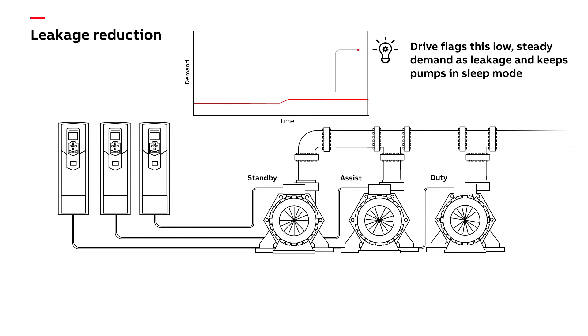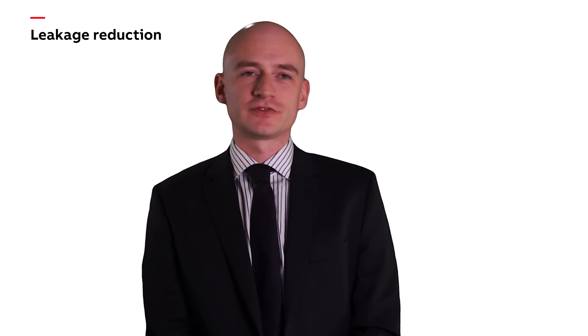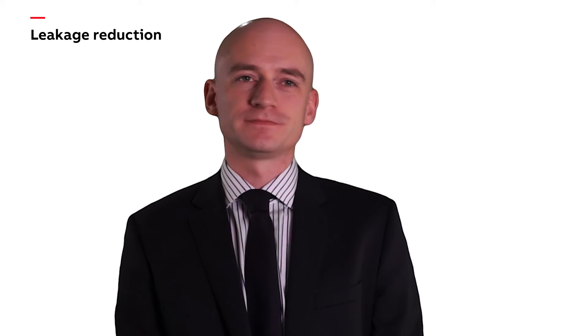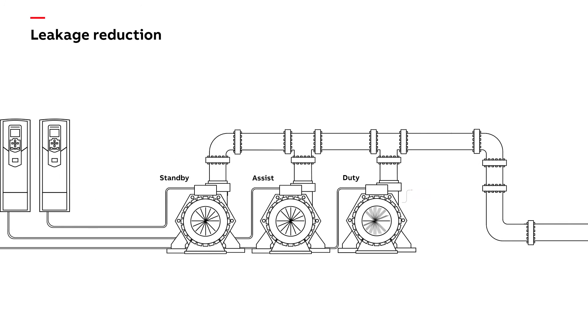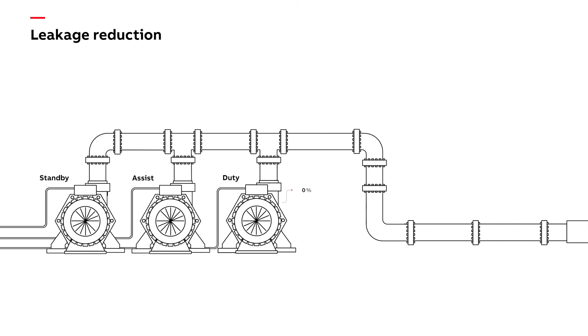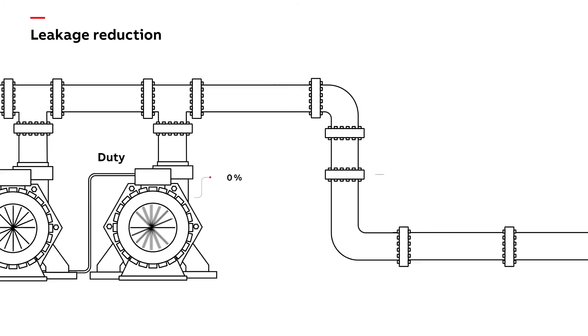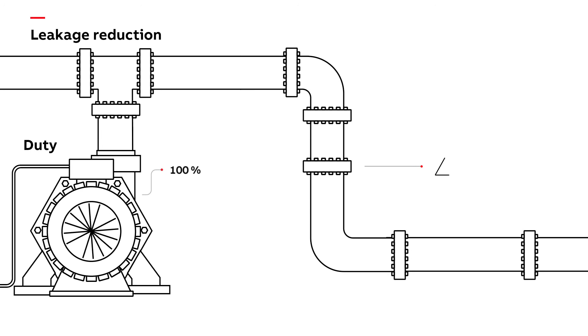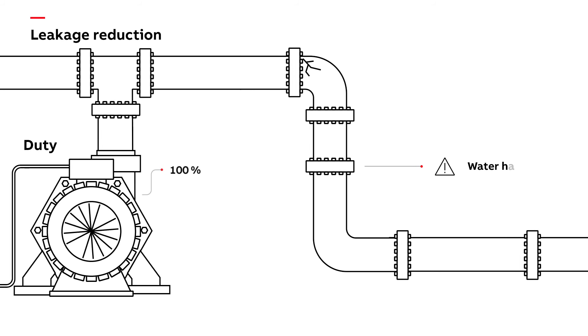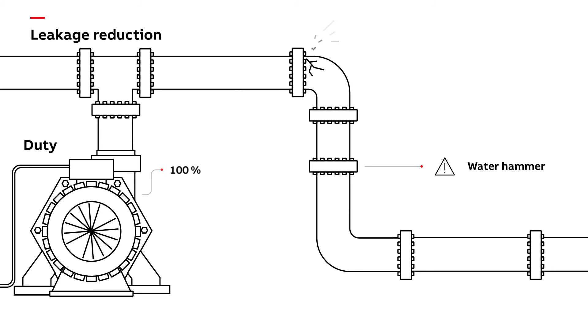Drives can also prevent leaks from occurring in the first place. Switching pumps on and off causes rapid changes in flow. These flow changes are followed by transients in pressure, causing an effect known as water hammer. This can damage pipes, pipe support, and causes leaks.